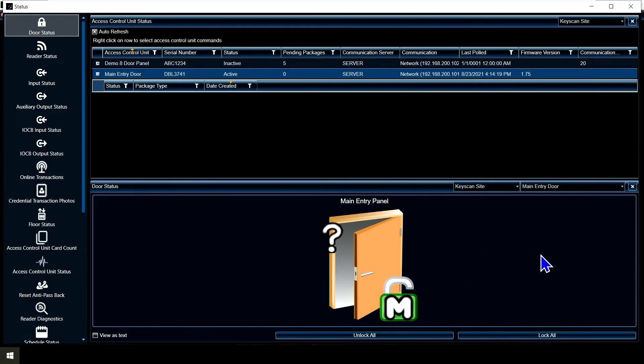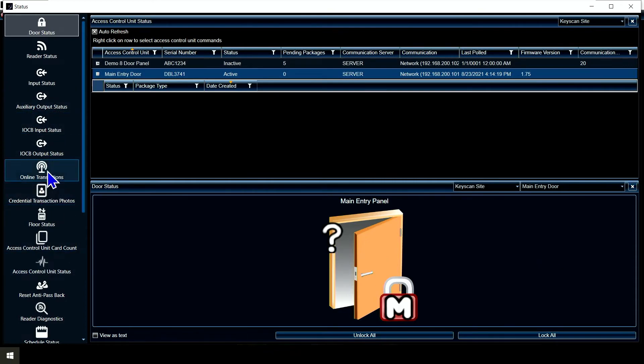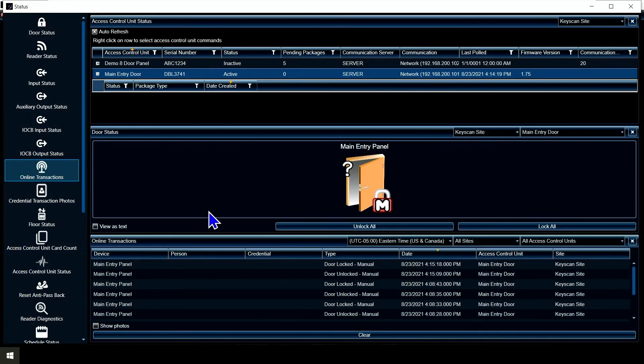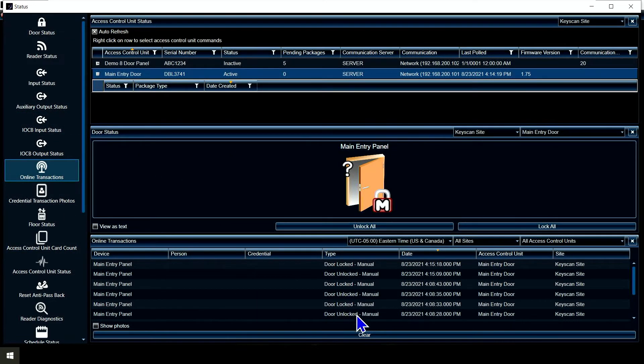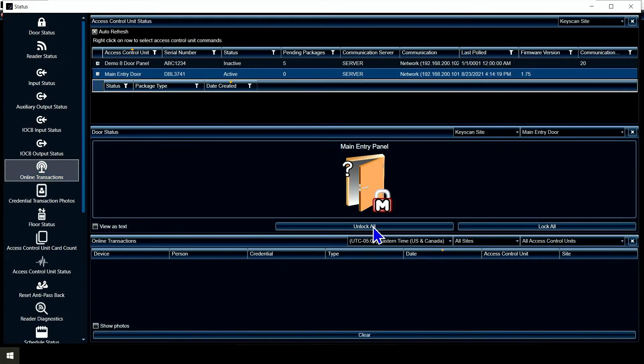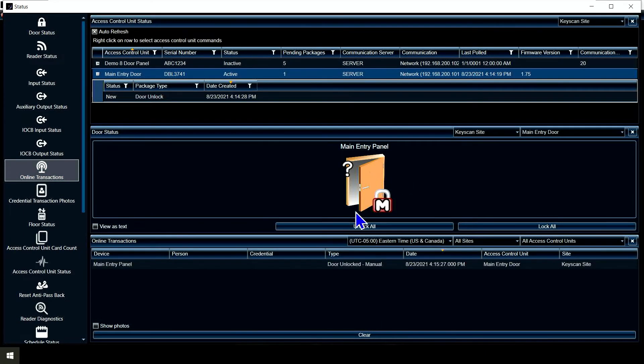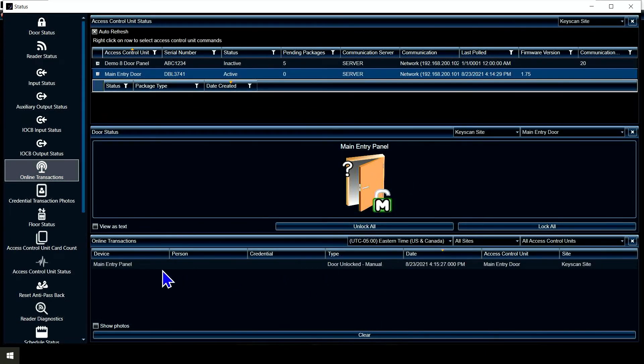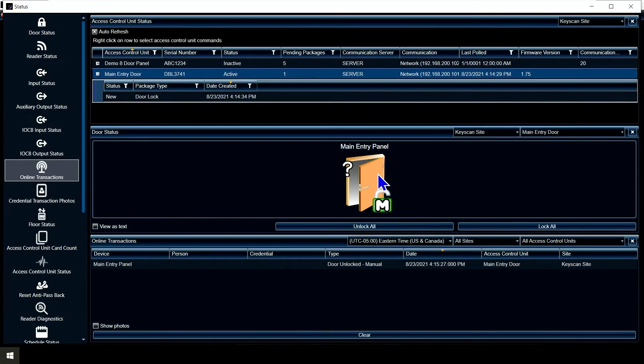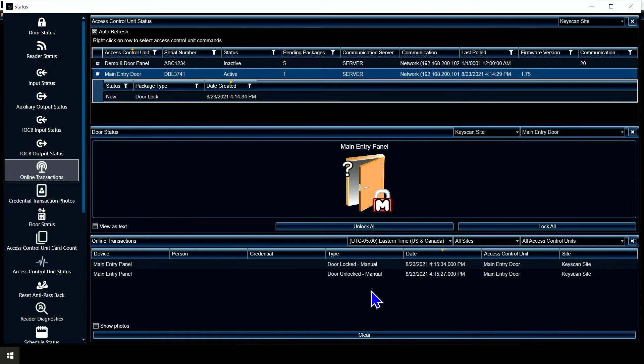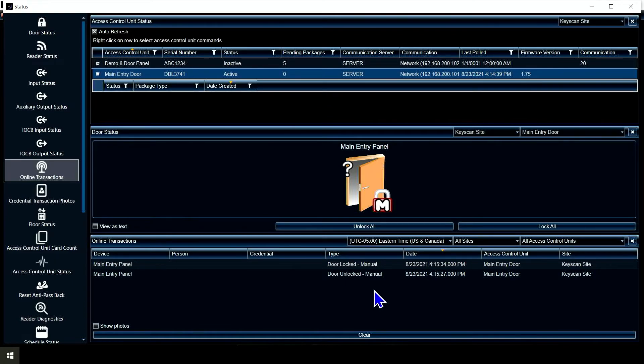I can actually pull up the online transactions here and I see a list. If I clear this list and I double click on the panel, I see on the list here live transactions: door unlocked manual, double click again, door locked manual. So I know I'm talking to the panel and it's talking back to me. Those are some of the things we want to look at to verify.